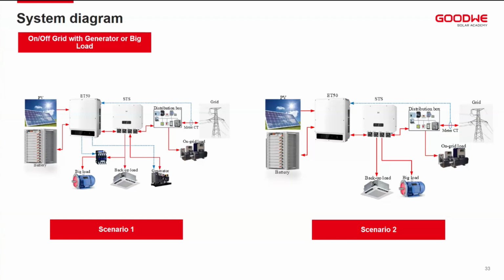As the battery starts discharging to particular SOCs, let's say 40 or 50% state of charge, the inverter can be automatically programmed so that at certain points, only very critical loads can discharge the battery. So we have a smart load disconnection signal from the inverter to the contactor to disconnect the big load. Then you're only left with the very critical loads to use up the battery charge. Now that's scenario one. And in case you're discharging your battery towards a very critical level, let's say 10% state of charge, then the inverter can also send a start signal to your diesel generator so that it starts up and powers the loads as we wait for the next day for the sun to come up and then the charging of the battery starts.